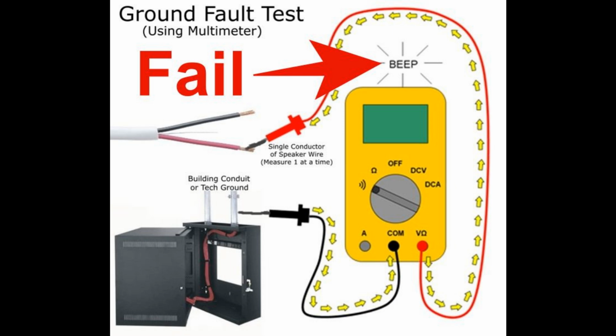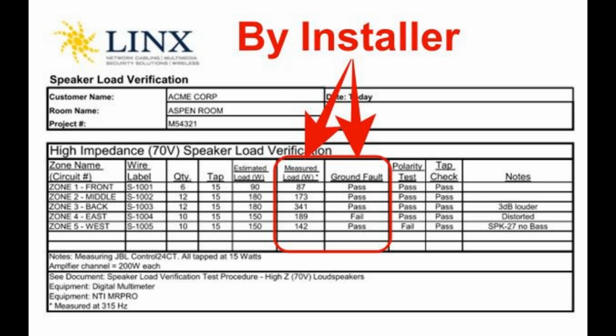Continuity indicates the speaker wire insulating sheath is most likely damaged, and the bare copper is somehow touching electrical building ground by metal conduit or junction box. Troubleshooting this type of problem can be very time-consuming. This is why the installation crew should perform this test just after wire pull.